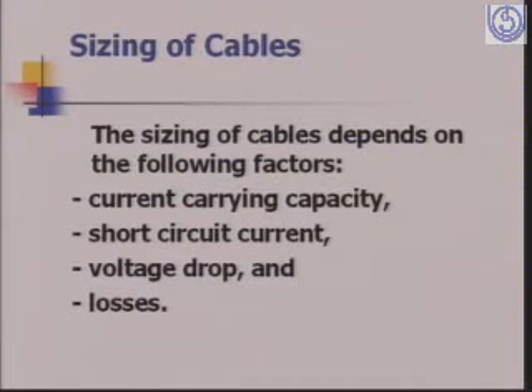The sizing of the cable depends upon its current carrying capacity, the short circuit current, the voltage drop, and the losses. Like the overhead conductor, we have to keep the voltage drop at the consumer premises within the limits, that is plus minus 6%. Even at 11 kV and 33 kV, the voltage limits are prescribed. So the sizing of the cable will depend on the voltage regulation which we want to achieve, its current carrying capacity, its short circuit current, and the losses.